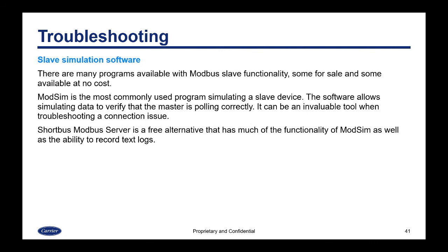There are also many programs available with Modbus slave functionality, some for sale and some at no cost. ModSim is the most commonly used program to simulate a slave device. The software allows simulating data to verify that the master is polling correctly. It can be an invaluable tool when troubleshooting a connection issue — if you're having an issue with the PLC connecting to the device, you can use ModSim to simulate the device and see if you get a response at the PLC. Shortbus Modbus Server is a free alternative that has much of the functionality of ModSim as well as the ability to record text logs.